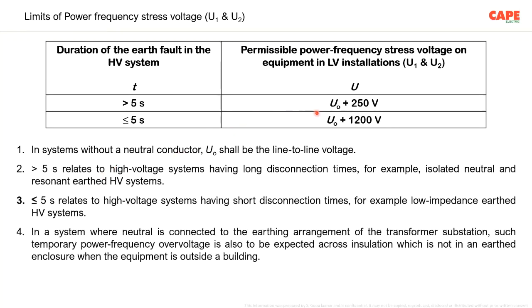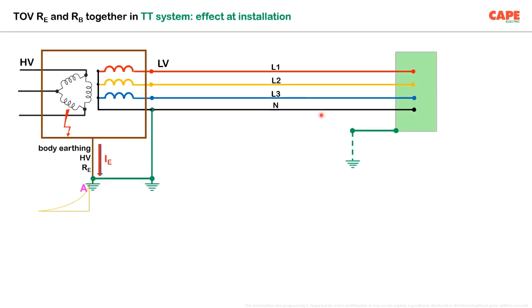So there are two things: higher than 5 seconds and less than or equal to 5 seconds. This depends on the high voltage supply, whether the high voltage supply is earthed, solidly earthed, or impedance earthed system. Not very important now because I have a better slide which I will show you. Say, for example, you have an electrical installation, something like this.